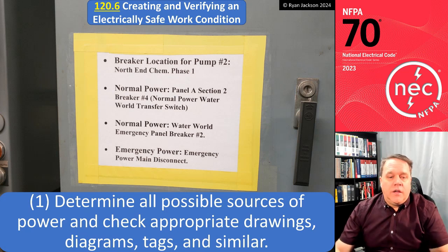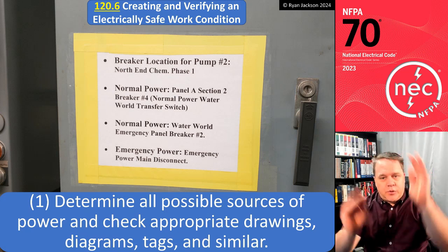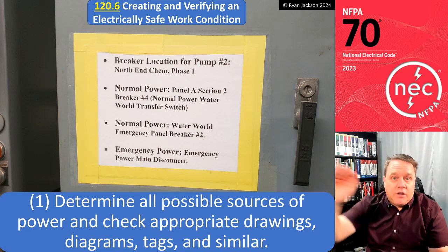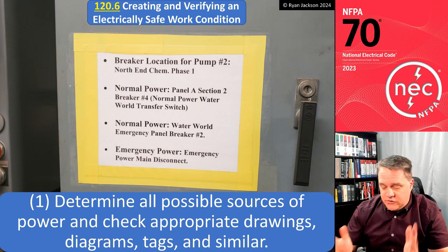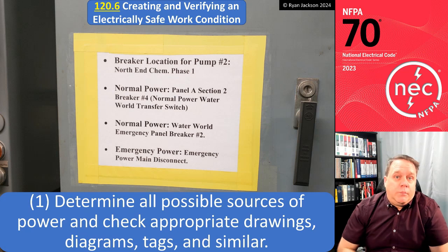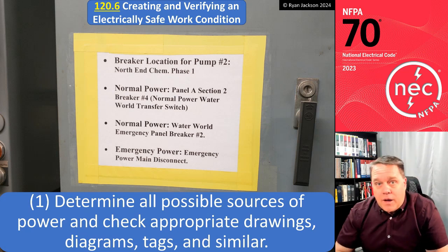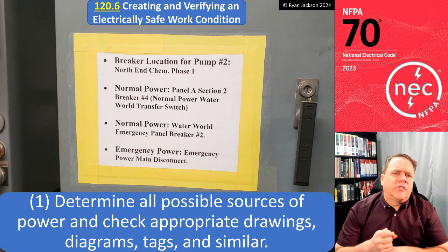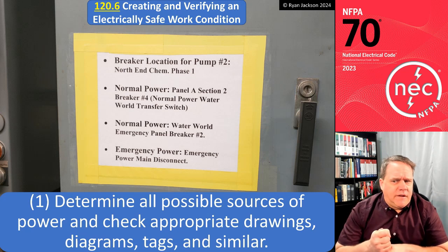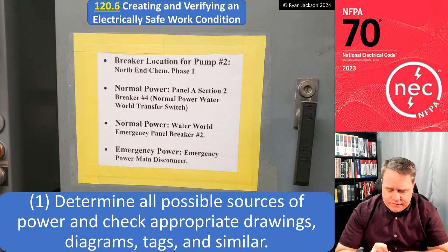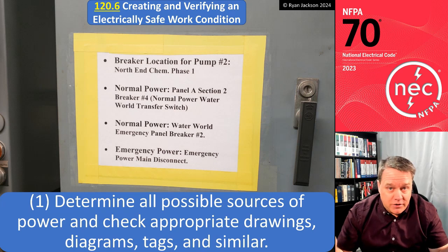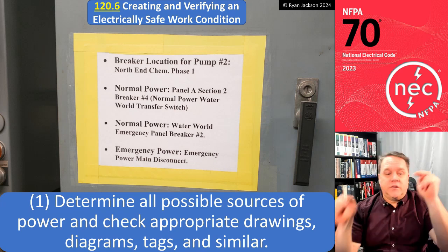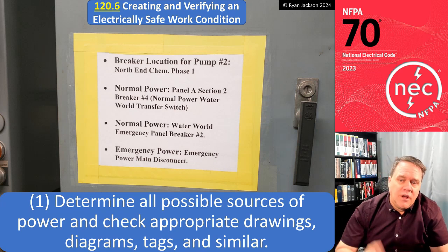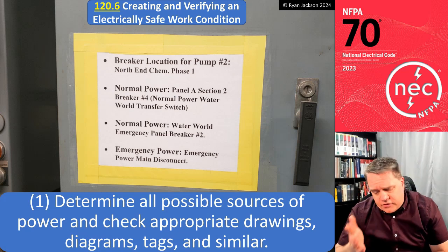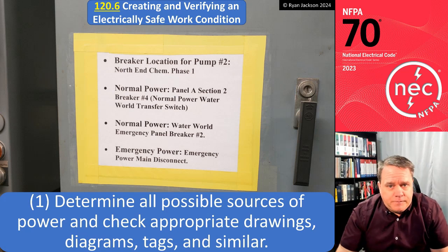So here at this facility, they've actually printed instructions telling you what needs to be shut off, because if it's just a matter of shutting off one breaker or one disconnect, that might be simple. What if it's got a UPS system? What if it has a battery backup? What if it has a generator, right? What if it's one piece of equipment that's supplied by 2 different circuits? So item 1, as I mentioned before, this can often be the most difficult part.